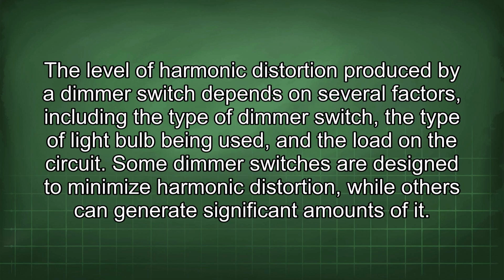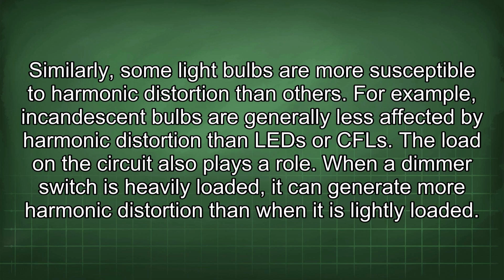The level of harmonic distortion produced by a dimmer switch depends on several factors, including the type of dimmer switch, the type of light bulb being used, and the load on the circuit. Some dimmer switches are designed to minimize harmonic distortion, while others can generate significant amounts of it. Similarly, some light bulbs are more susceptible to harmonic distortion than others. For example, incandescent bulbs are generally less affected by harmonic distortion than LED or CFL. The load on the circuit also plays a role. When a dimmer switch is heavily loaded, it can generate more harmonic distortion than when it is lightly loaded.